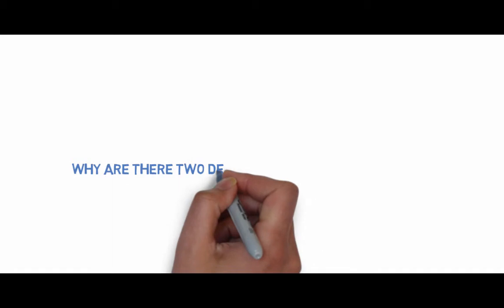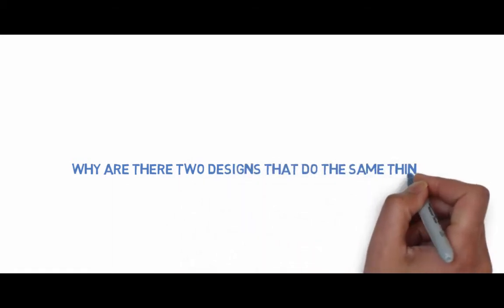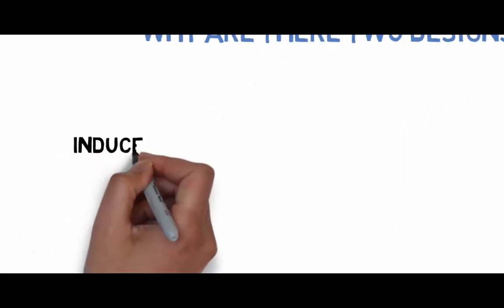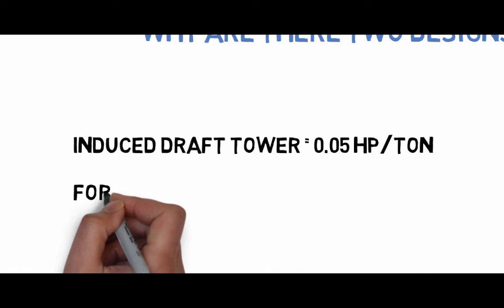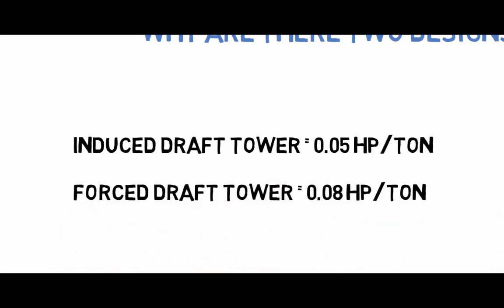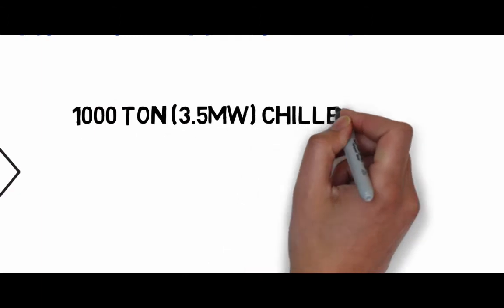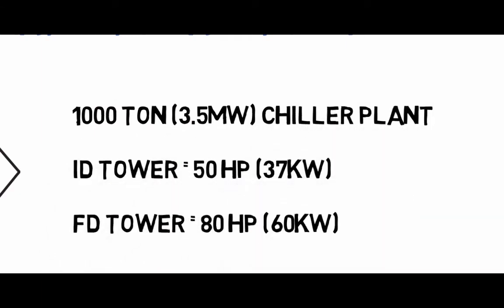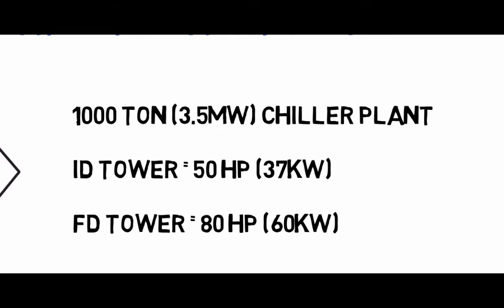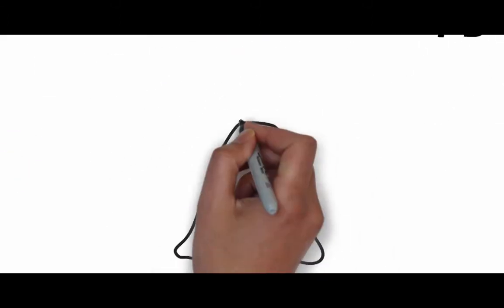So a logical question is: why are there two tower designs that do the same thing? Induced draft towers are typically preferred over forced draft because they require less energy to do the same job. Induced draft towers typically require about 0.05 horsepower per ton, while forced draft towers typically require about 0.08 horsepower per ton. In a 1,000-ton or 3.5-megawatt chilled water plant, that means a 50-horsepower or 37-kilowatt tower versus an 80-horsepower or 60-kilowatt tower — which over the course of the tower's lifetime can be a difference of tens of thousands of dollars in operational costs.